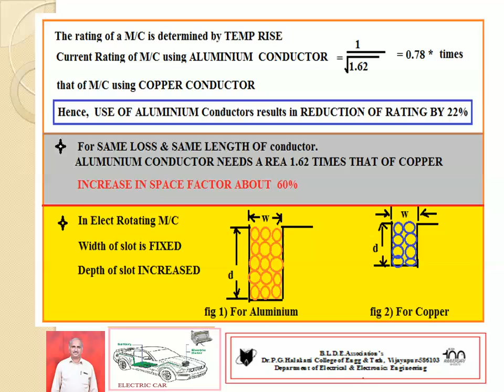Hence, here the two slots are shown: one with copper as the winding material, and one with aluminium as the winding material. Keeping the width of the slot the same, the increase in area can be met by increasing the depth of the slot. It can be observed in the aluminium winding, figure number 1. In the copper winding, the depth of the slot may be equal to 1 meter. In aluminium, it may be equal to 1.6 times that of copper. This is the understanding.